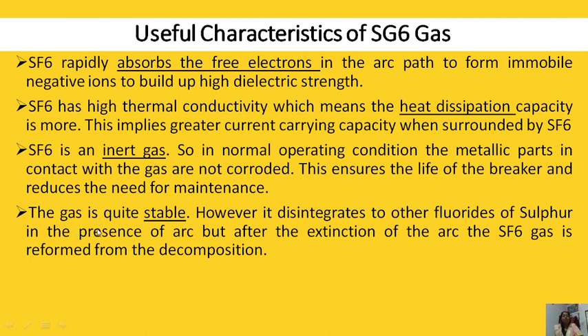One important property: the gas is quite stable. Stable means that whenever an arc forms there is ionization, and when the arc gets extinguished there is a deionization process. Between ionization and deionization the gas gets decomposed — it gets converted into fluoride of sulfur ions. After the arc gets extinguished, it reforms into its original form. So even though it disintegrates to other fluorides of sulfur in the presence of an arc, after extinction the SF6 gas is reformed from the decomposition.